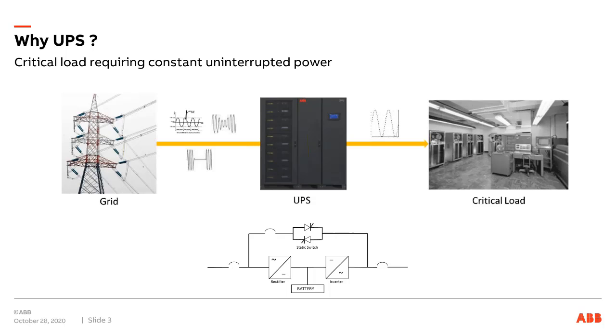One extra comment on this is that UPS manufacturers have found out, as customers have really been pushing for higher efficiency, that if you leave the UPS on the static bypass, it's got very high efficiency, just over 99%. In the business, it's referred to as economy mode. The UPS is in bypass, so it doesn't offer the filter function that a UPS normally will. But even in that mode, the inverter is at that point asleep, but if power from the utility should fail, it can still kick in and start feeding power from the battery to the load. It's not a new function. It's been around in the UPS business for a couple of decades. Hardly any customers use it because it's not a full UPS function. So much about that.